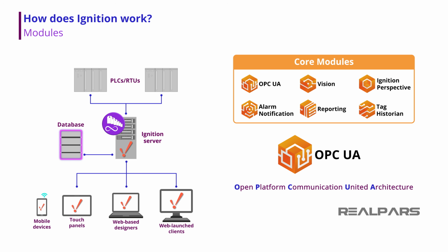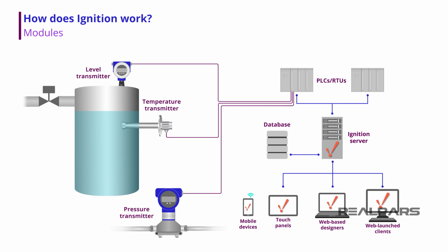Tags and databases are the backbones of a SCADA operation. For example, let's think of a plant floor tank fitted with level, temperature, and pressure transmitters. Those transmitters send a raw data signal back to the PLC, which may have some form of scaling or other logical manipulation and is stored as a tag. This tag is what ends up being used and displayed in a SCADA application. Depending on your industrial application, you can have hundreds or even thousands of tags or database points.